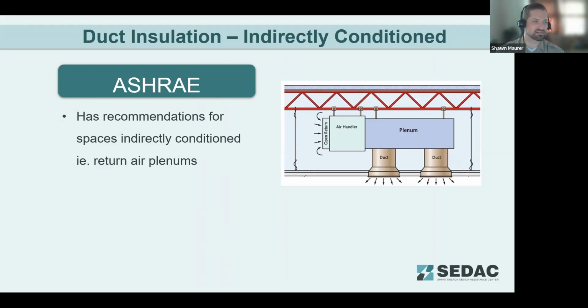This might be semi-conditioned, semi-heated spaces, where the IECC considers spaces as either fully conditioned or unconditioned. So here they're looking at return duct insulation, which isn't required in those spaces because there's not a great temperature difference. If the return is pulling air from a plenum space or indirectly conditioned space, there shouldn't be any temperature difference there. But on the supply side, you do need at least that R1.9. The duct insulation is helpful for preventing condensation and rust on the ducts, so it maintains the longevity of the system, and you're reducing the heat loss from conditioned air to this semi-conditioned space.